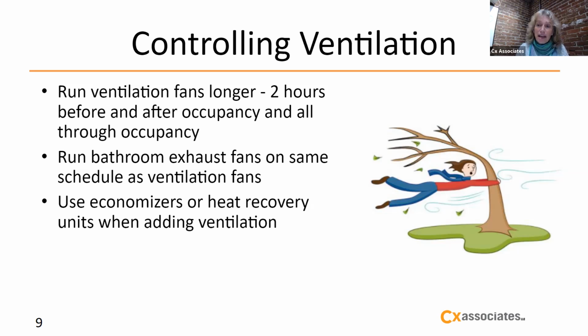And then if you don't have ventilation, and we'll get into those details in just a minute, there's a lot of buildings in Burlington especially, but throughout Vermont, that have baseboard heat and have no ventilation or air conditioning. So if you have baseboard heat, and maybe a heat pump for cooling, you don't have mechanical ventilation bringing fresh air into the building. In the summer, opening windows is great. In the summer and in the shoulder seasons, you can use economizers to bring in more fresh air. In the winter, you'd really want a heat recovery unit, and if you have no ventilation, the easiest thing is to just put in a heat recovery unit for the entire year. Next slide, please.